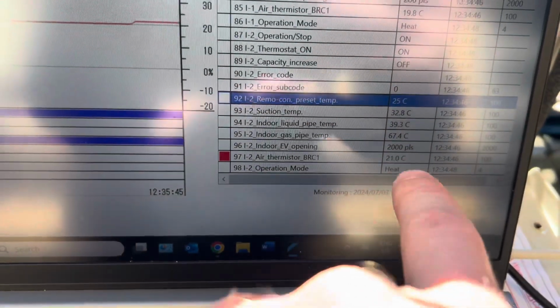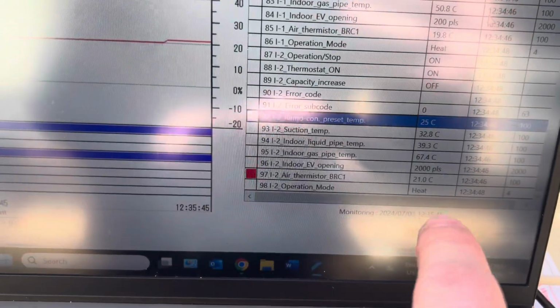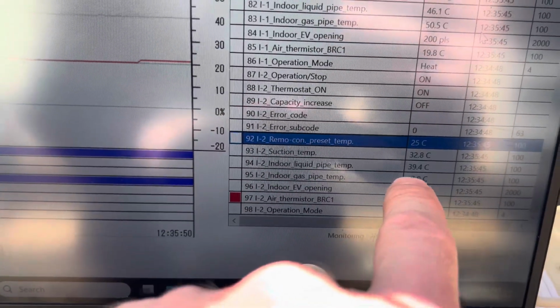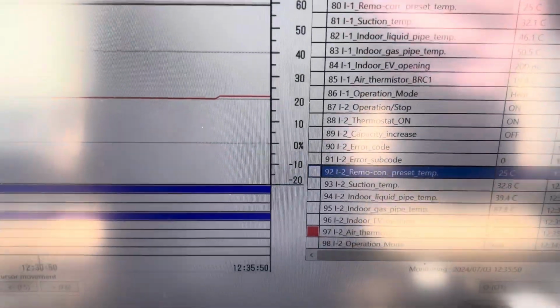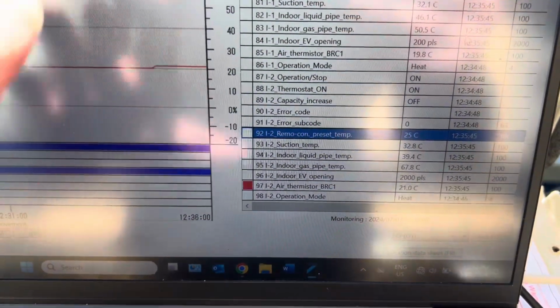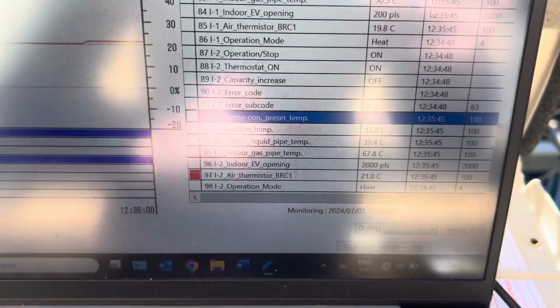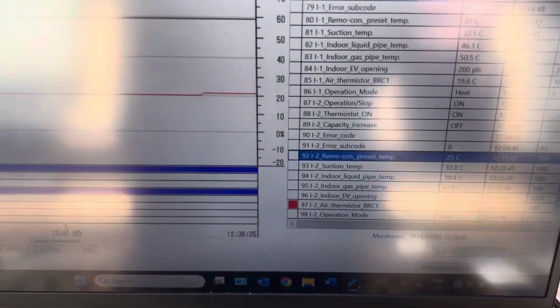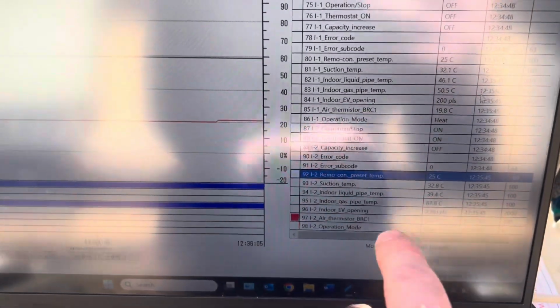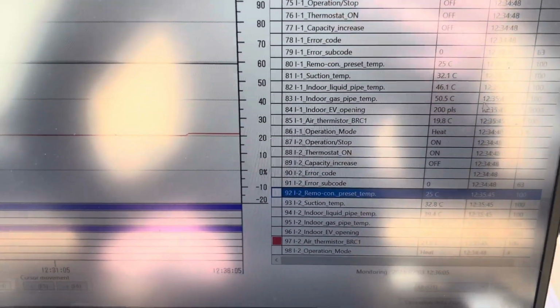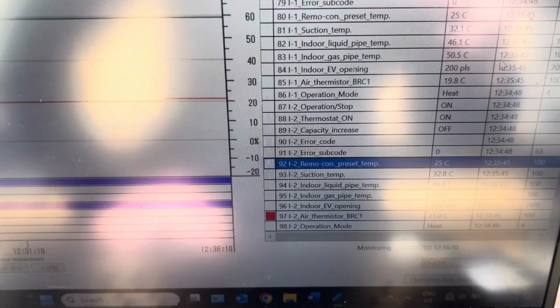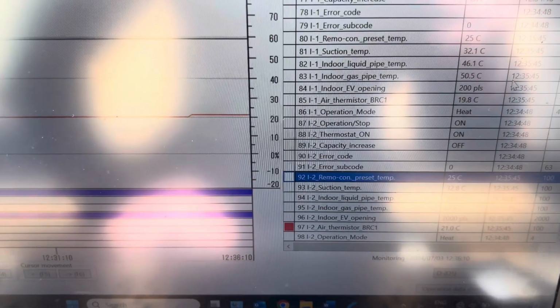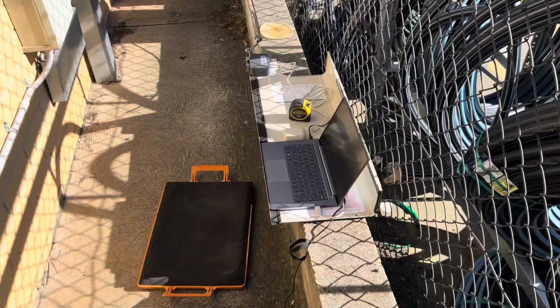So pretty much trying to get the liquid pipe temp up, right? So it's reading 5K between that liquid pipe temp and then the transducer, high pressure transducer at the outdoor unit. And it'll keep opening until it gets there, but it's just not getting there, right? So what I might do, sometimes they'll have like fresh air supplies to the unit, and that can kind of throw off your liquid pipe temp readings or your coil readings anyway. I don't think that's the case here actually, but let's just, we'll go in and have a quick squiz at that indoor unit just to have a look at something I'm thinking of.